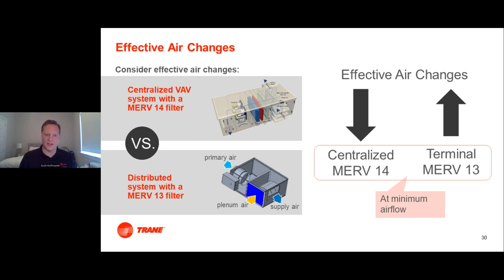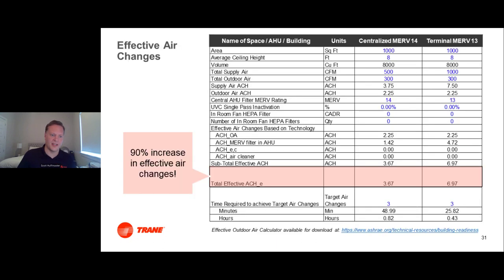For some quick comparison, let's consider either upping our filtration centrally at an air handling unit to a MERV 14 filter, and let's compare that to a system where I put a MERV 13 out in the space. So we're going to put it in a distributed system. What's an example of a distributed system? Let's say a series fan power box, something served with a DOAS, where you've got that out in the space. Now, one would think if I have a MERV 14, that's better than MERV 13.